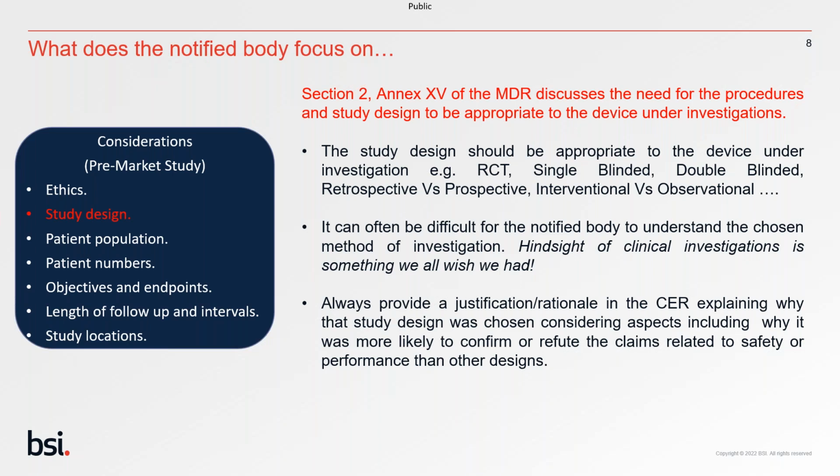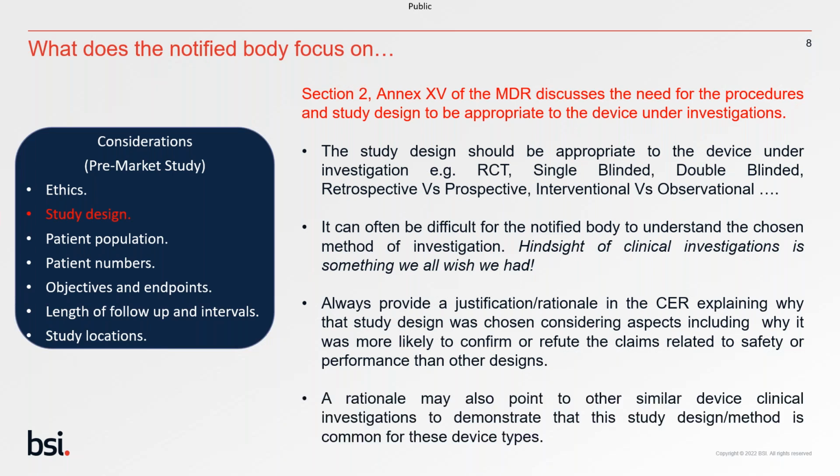And also think about why that specific study design was chosen, and is it because it was more likely to confirm or refute the claims related to safety and performance than other designs of investigations? Also, what's helpful to the notified body is where you talk about the clinical investigations for maybe similar devices, where you say, well, actually, typically for this group of devices, historically, these 5 devices have had this style of investigation that allows a better comparative result.